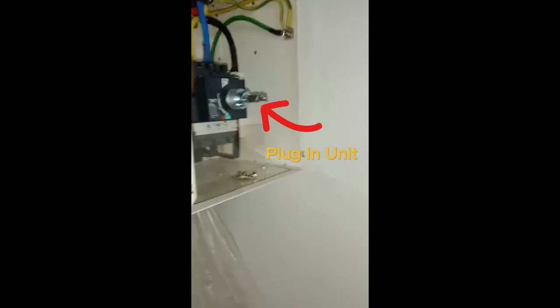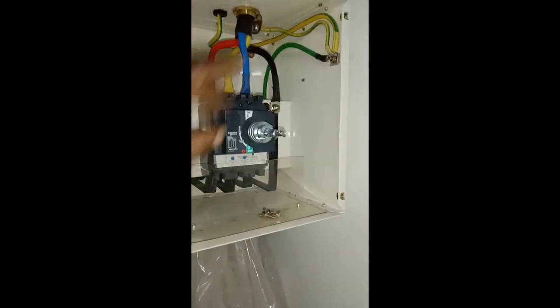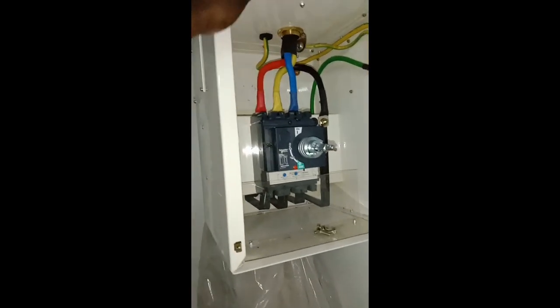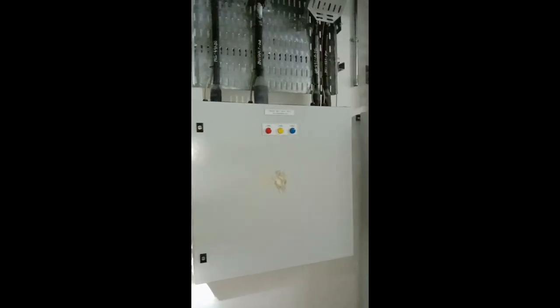Moving to the SMDB and power feeders: the incoming supply comes from Busduct 2 going into the bus bar box. Inside the bus bar box we have a circuit breaker with termination done. The cable is pulled from the bus duct and terminates to the SMDB as the incoming supply, with outgoing feeders going to the MCC, DB, and pressurization fan.